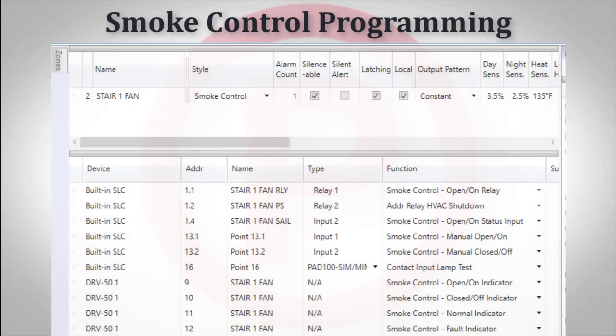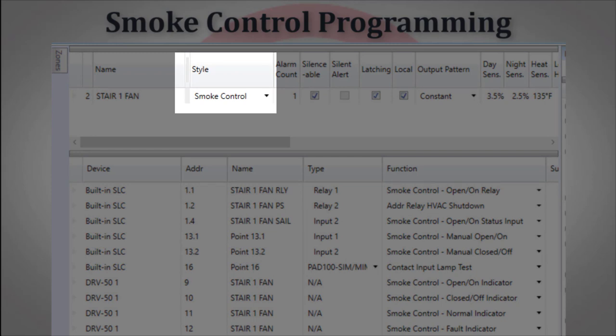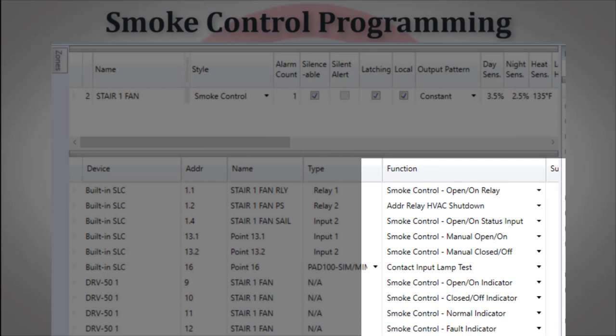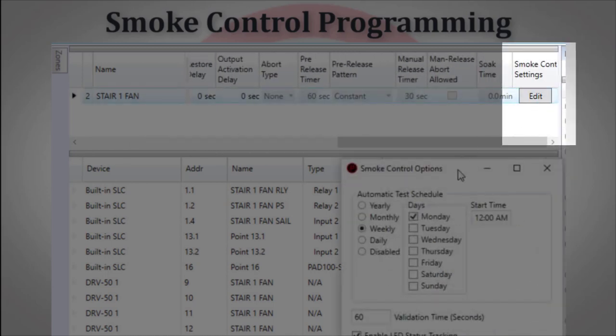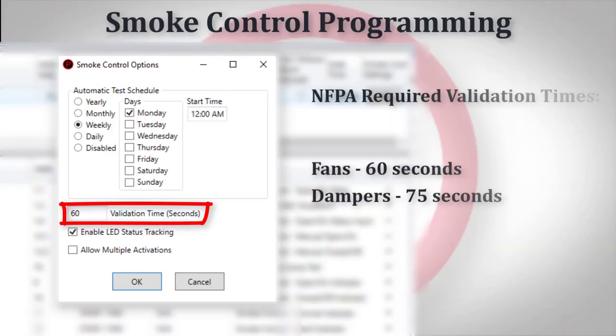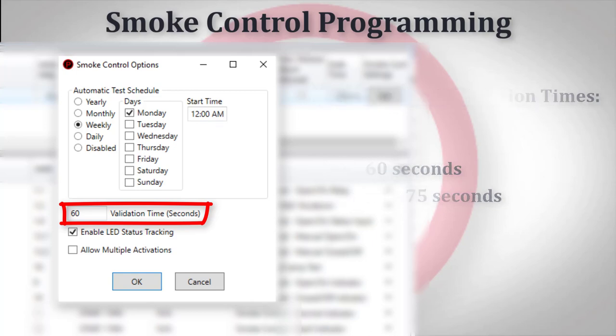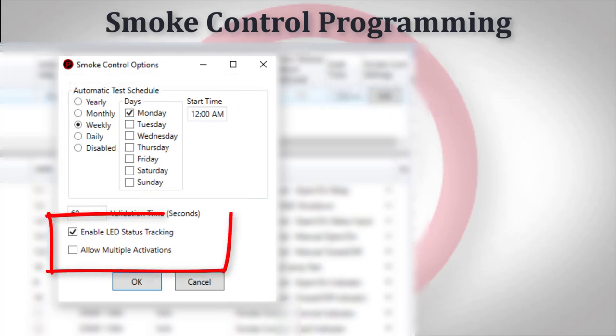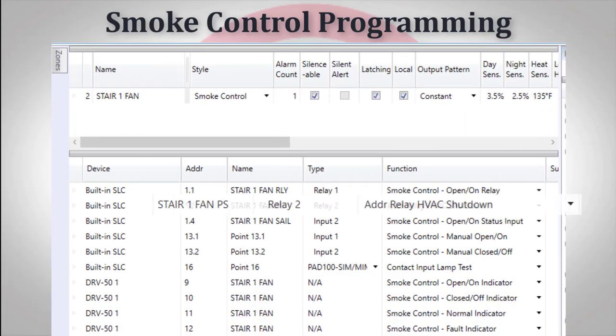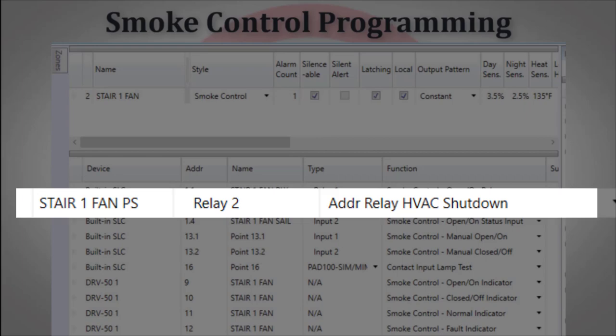In addition to specific smoke control point types, the fire panel programming software also contains a smoke control zone style. All smoke control point types must be assigned to a smoke control zone, except the manual override, which does not get assigned to any zone. The smoke control style zones contain validation timer settings for positive feedback from fans or dampers — NFPA requires a 60-second validation time for fans and 75 seconds for dampers. These zones also contain settings for the weekly test required by NFPA for dedicated smoke control systems, check boxes to enable LED status tracking and to allow multiple activations. Additionally, relays configured as HVAC shutdown, when added to a smoke control zone, will be activated by any input in that zone.